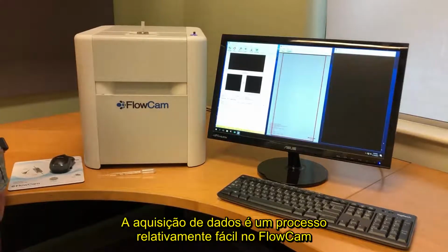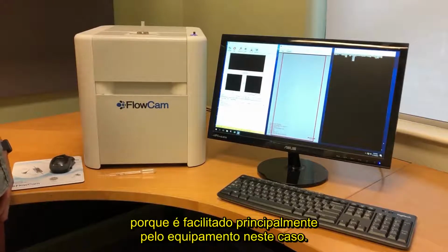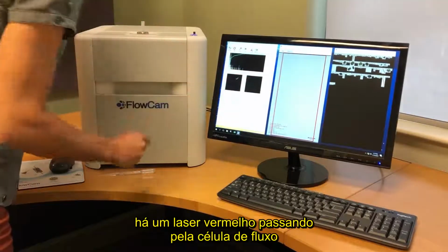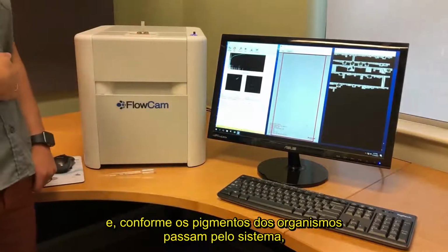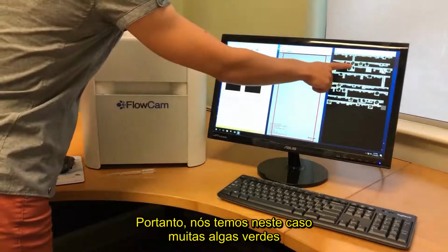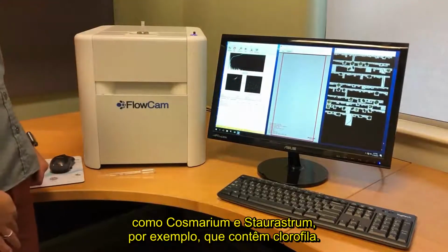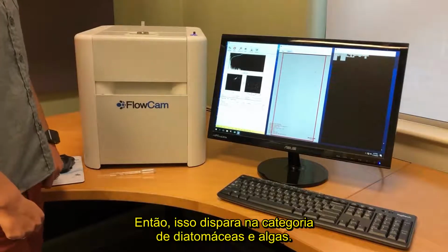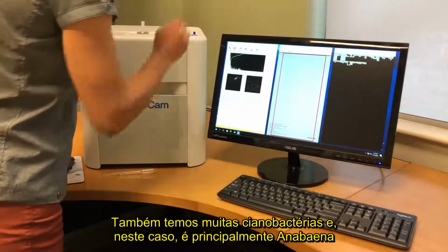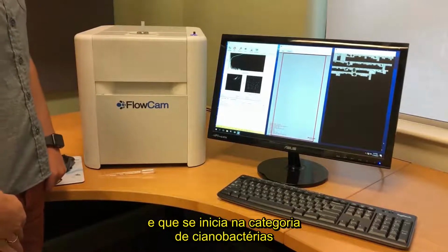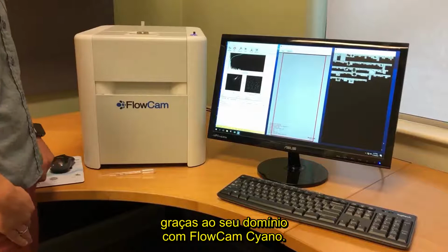Data acquisition is a relatively easy process on the FlowCam because it's facilitated primarily by the equipment. As we draw the sample through the system, there's a red laser beaming across the flow cell, and as pigmented organisms pass through the system, it triggers the camera to take a picture. In this case we have lots of green algae, so Cosmarium and Staurastrum, for example, that contain chlorophyll A. That triggers into the diatoms and algae category. We also have lots of cyanobacteria. In this case, it's primarily Anabaena, and that triggers into the cyanobacteria category thanks to its dominance with phycocyanin.